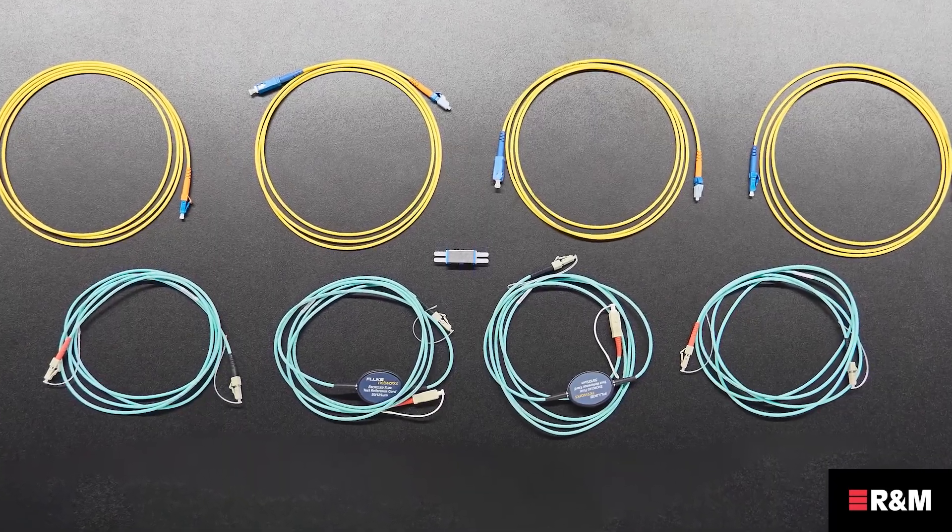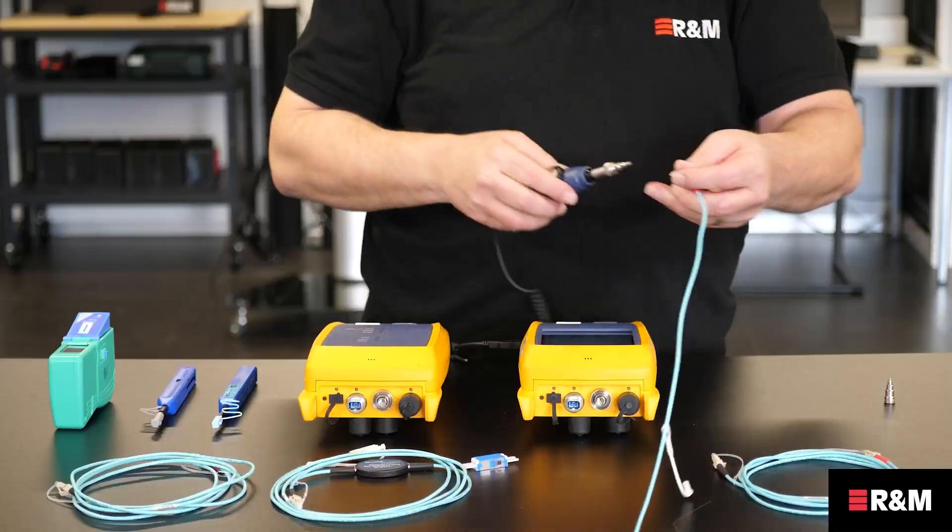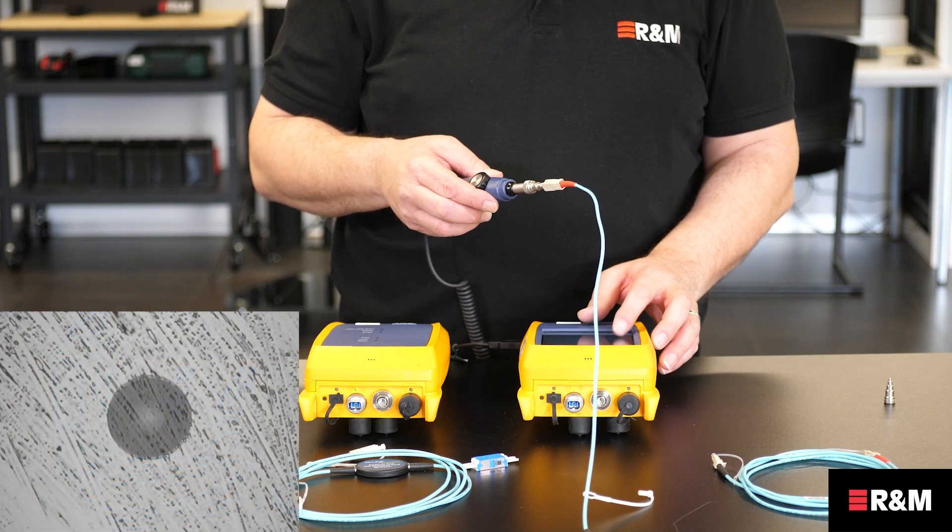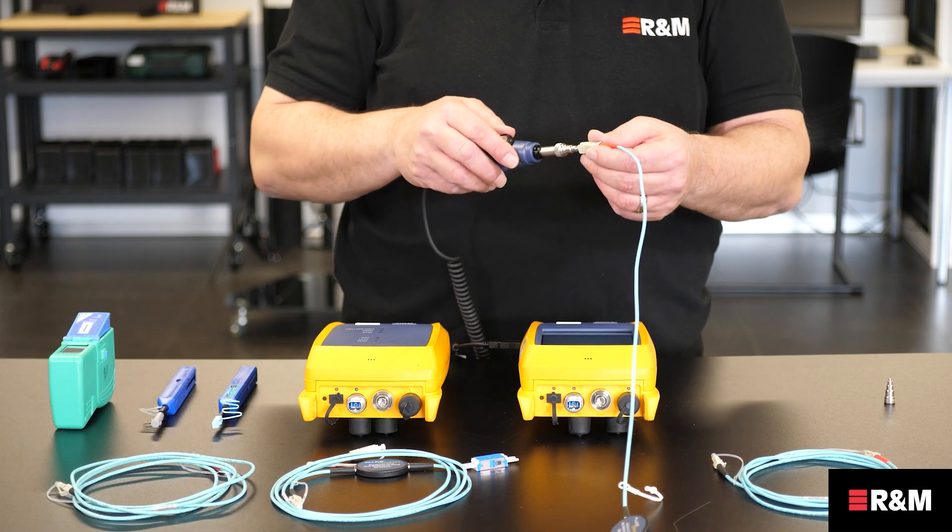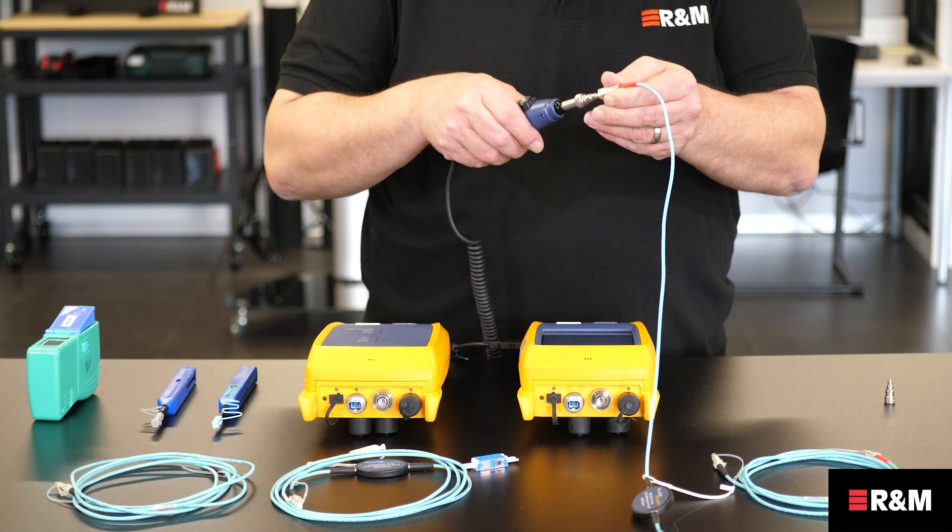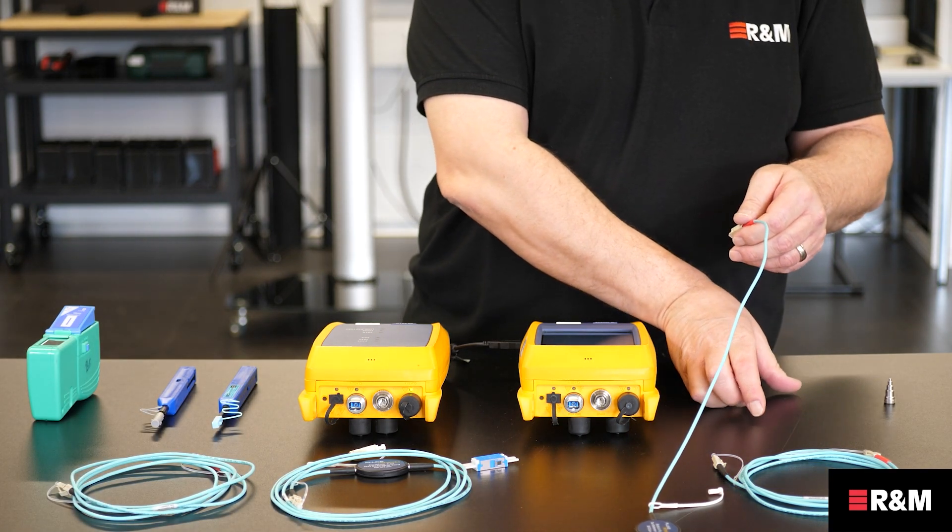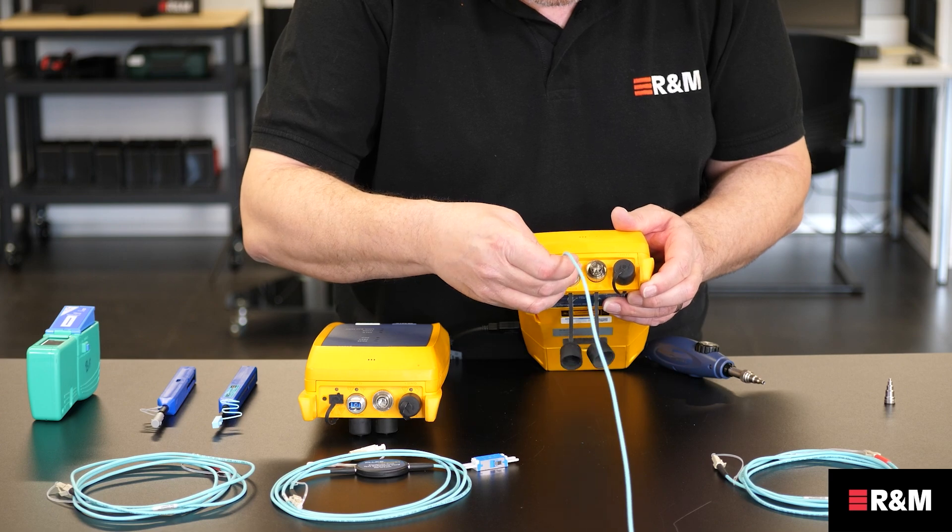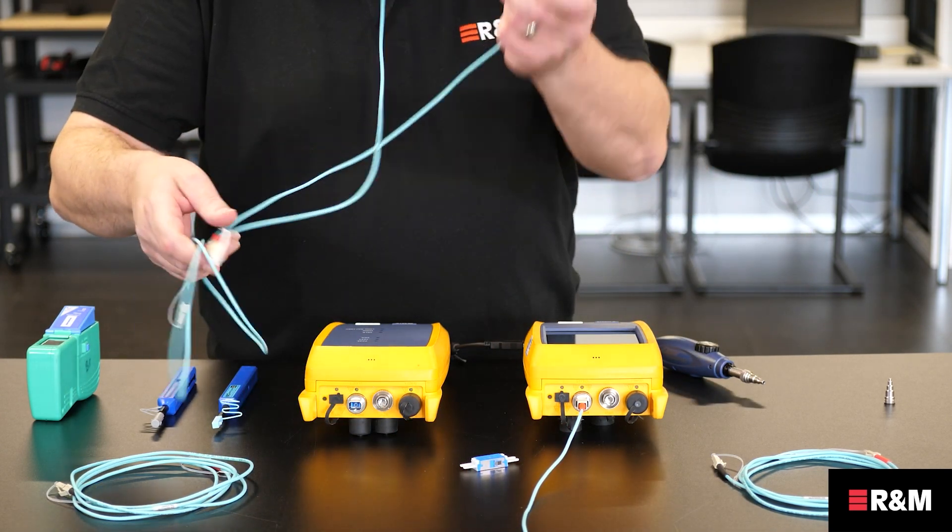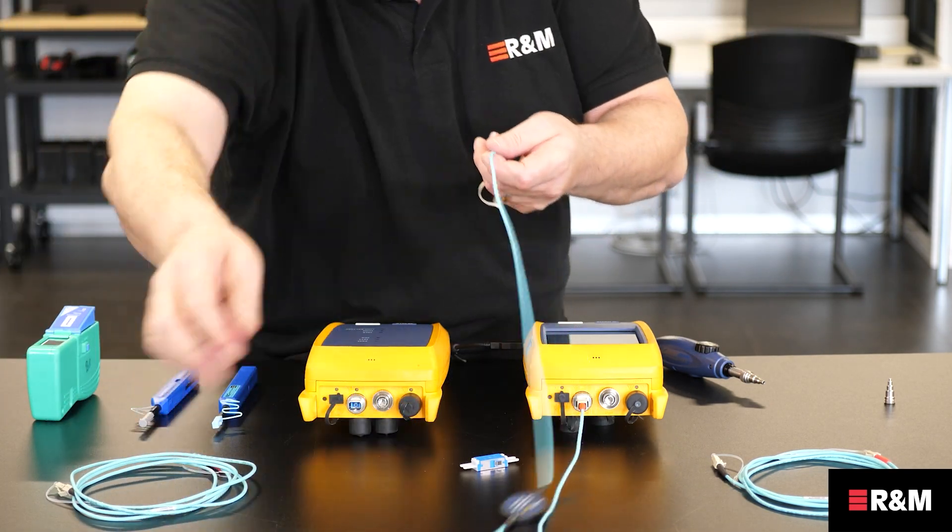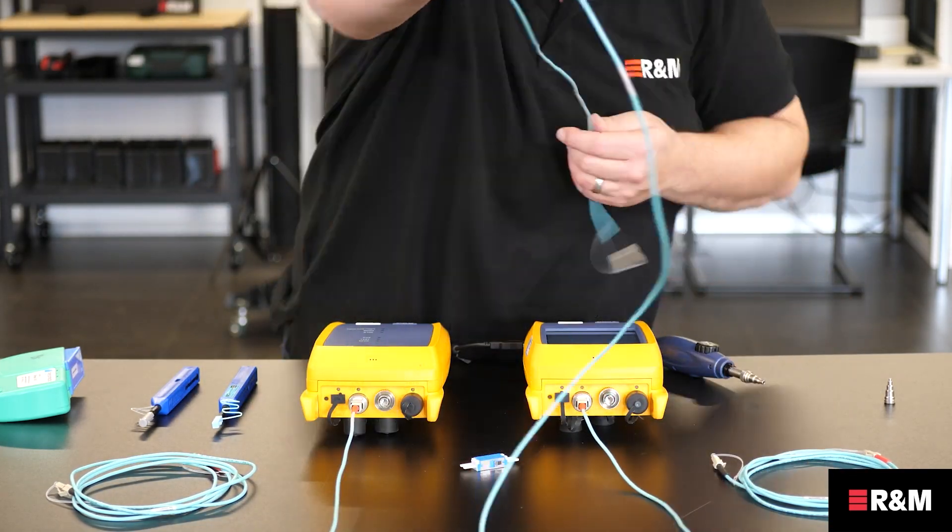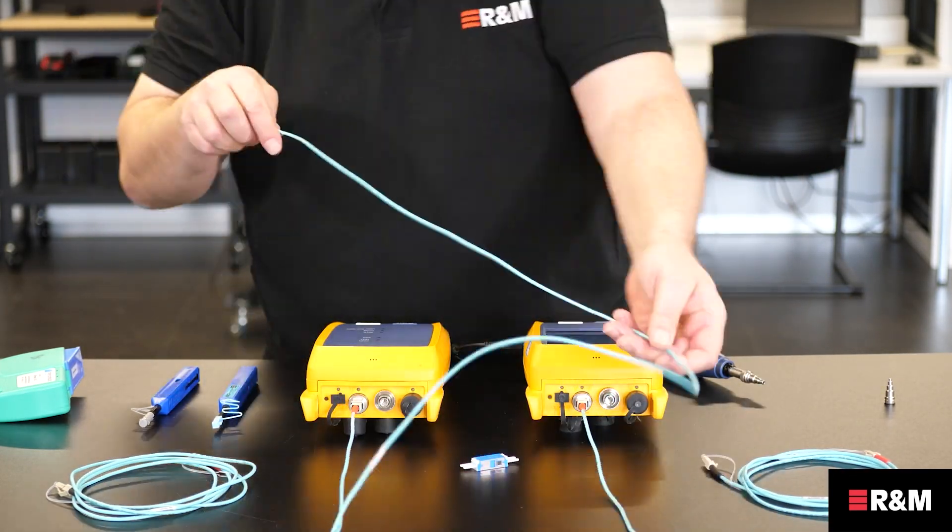Next, we need to prepare the test reference cords. This is done firstly by inspecting the end face. Only if it is dirty do you need to clean it. Please re-check after cleaning to ensure the end face is truly clear of dirt. Once cleaned, it can be inserted into the main tester. This procedure must then be repeated for all ends of the reference cords before being connected to the main and remote testers. Please note that many manufacturers recommend that you measure the loss of your test reference cords each time you set the reference.